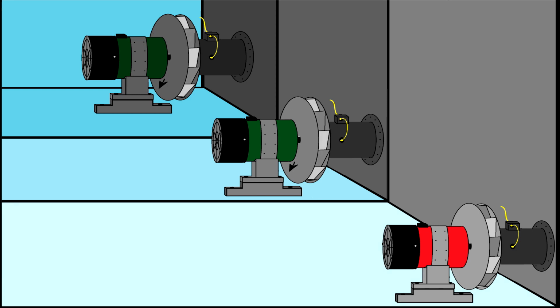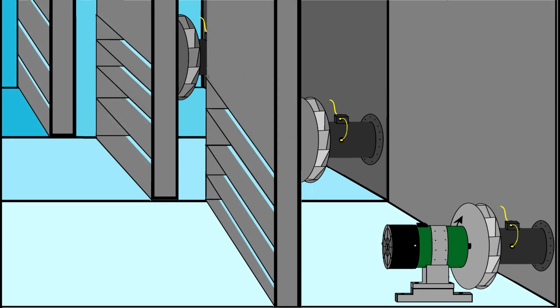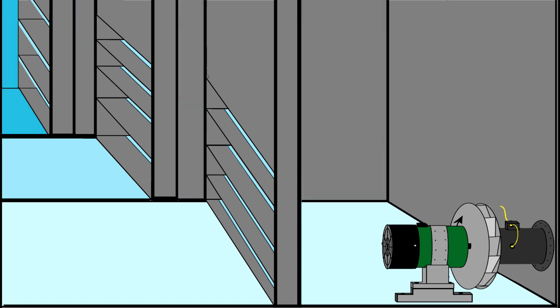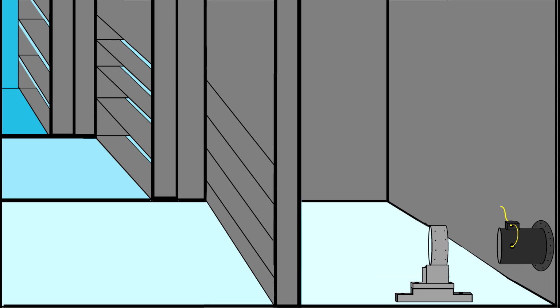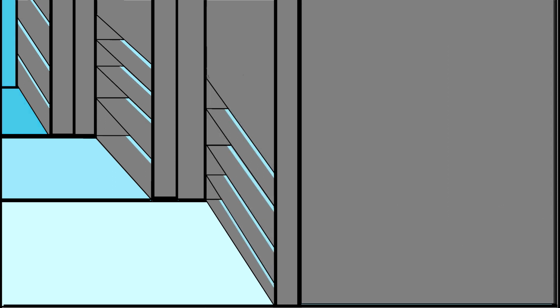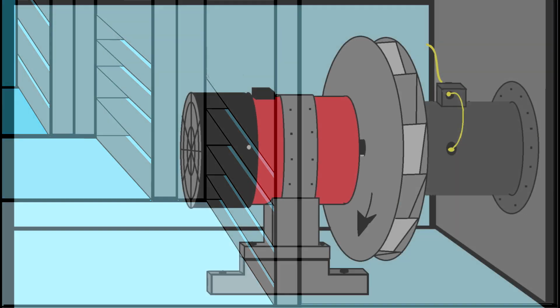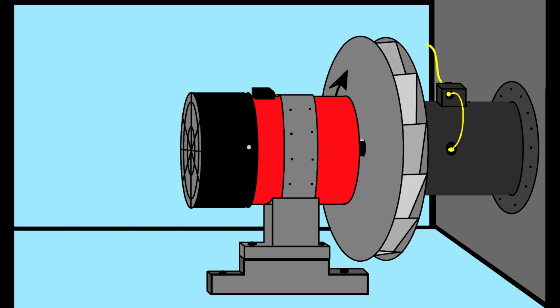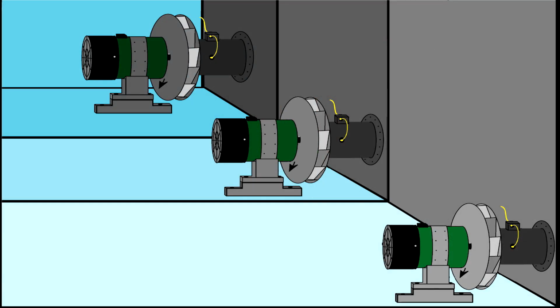This system is good because if one fan fails, the other two will take over and maintain the airflow. The benefit of it is that if one fan gets faulty, then in an individual chamber, the damper will isolate the premises. I can remove the fan and take it to repair while the airflow will be undisturbed. I don't like this particular fan arrangement because running inside the supply air chamber generates heat, and I have to compensate for that heat by choosing a slightly more powerful heat exchanger, because you guys know every motor will generate heat. You have to know how many kilowatts of heat that motor is generating.